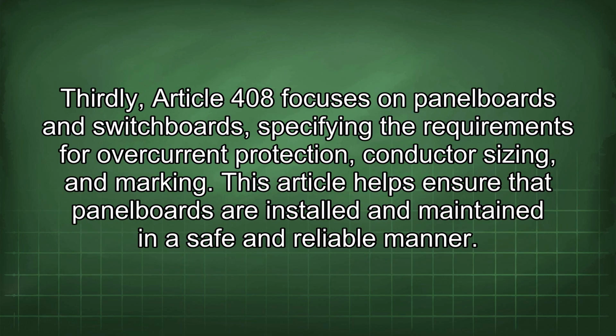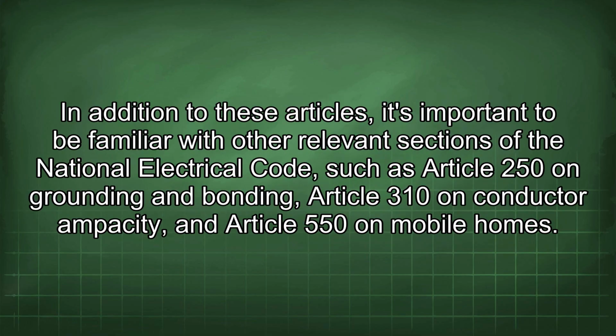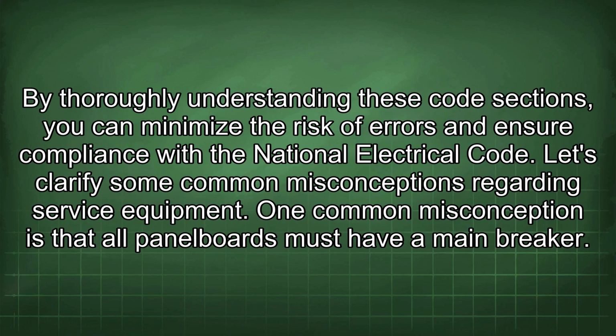Thirdly, Article 408 focuses on panel boards and switchboards, specifying the requirements for overcurrent protection, conductor sizing, and marking. This article helps ensure that panel boards are installed and maintained in a safe and reliable manner. In addition to these articles, it's important to be familiar with other relevant sections of the National Electrical Code, such as Article 250 on grounding and bonding, Article 310 on conductor ampacity, and Article 550 on mobile homes. By thoroughly understanding these code sections, you can minimize the risk of errors and ensure compliance with the National Electrical Code.